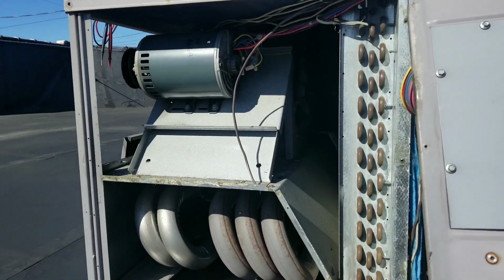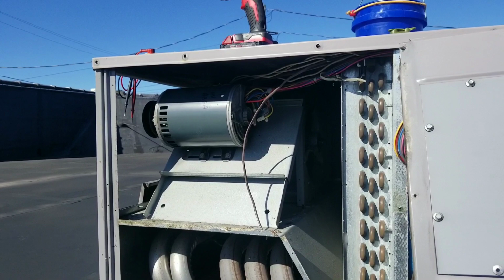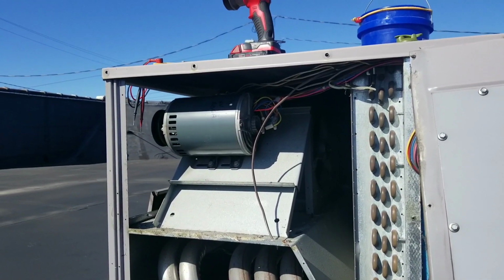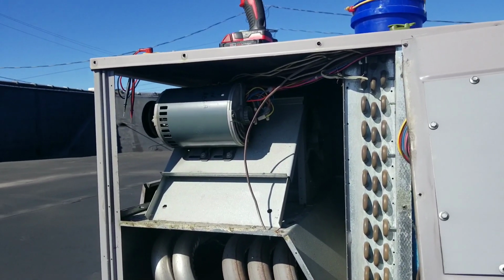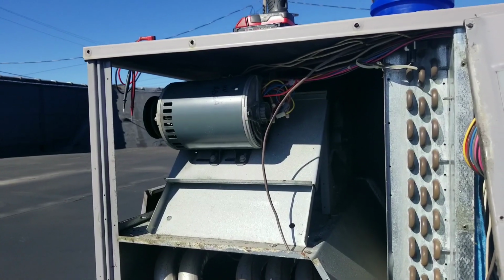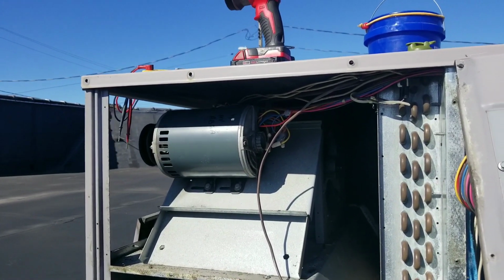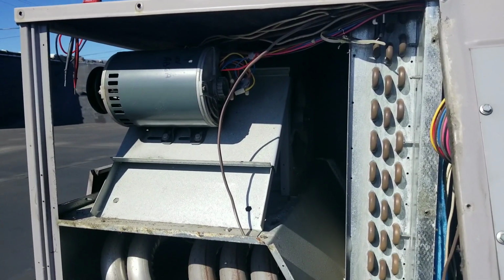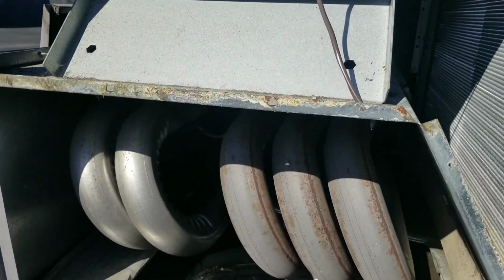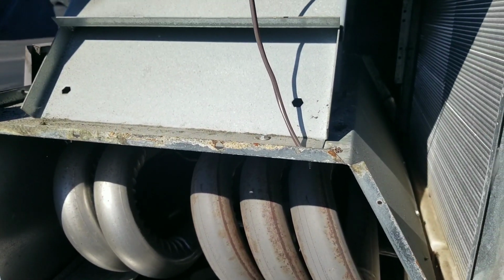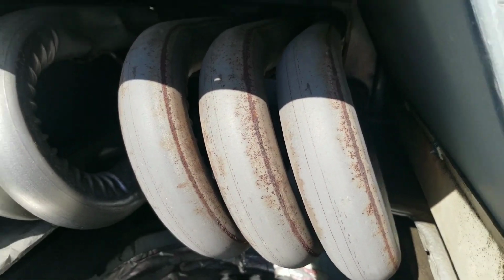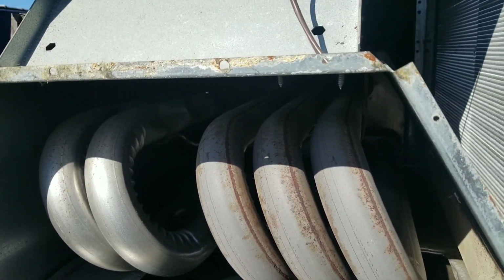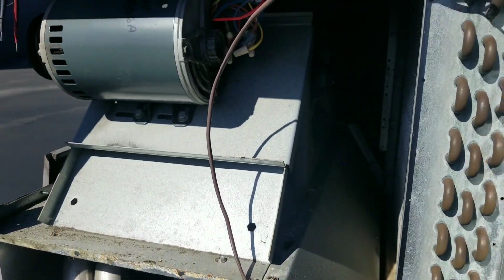Alright guys, as you can tell, I got the side panel pulled off to expose our blower motor. I prefer to do it this way rather than try to unmount that motor and pull it out the front to inspect the wiring. It's just easier this way. Plus, I can inspect my heat exchanger while I'm at it, which is getting pretty bad. You can probably get maybe another year out of this if they're lucky. But anyway, into our blower motor here.